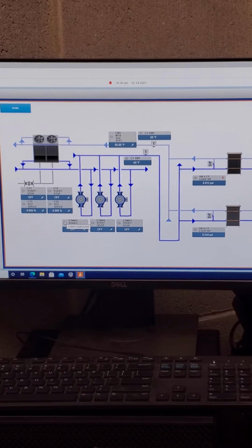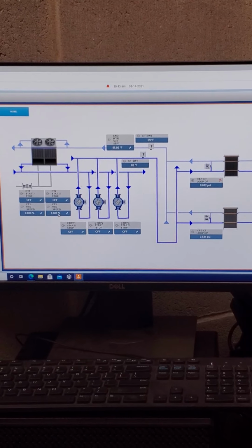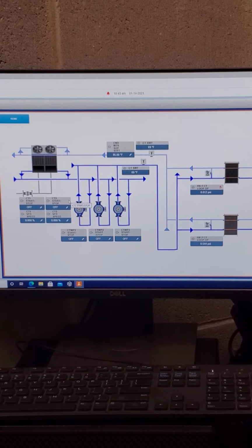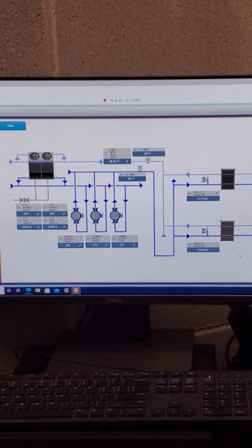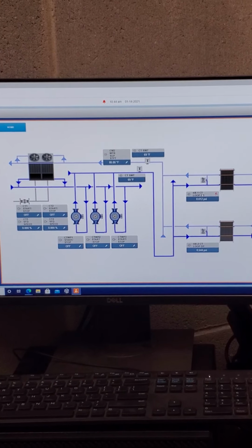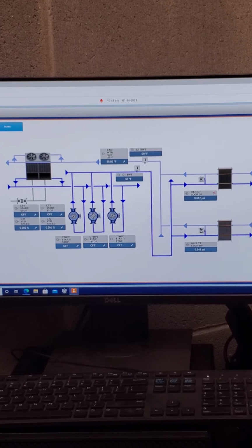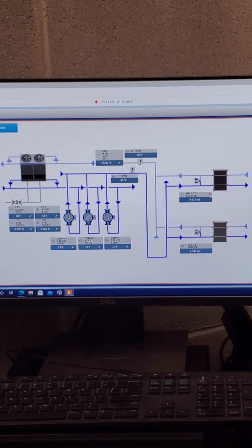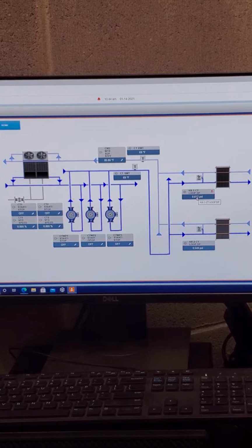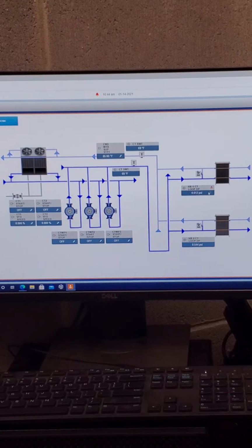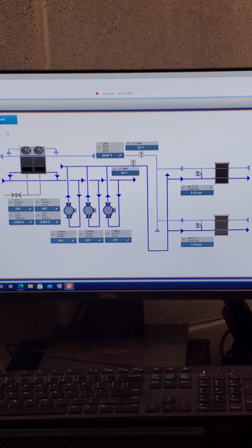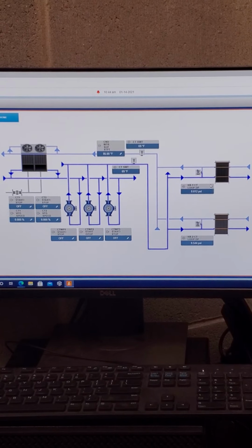We still can see, let me think here, I believe we still have a proof on this. We should still see an alarm if they're not running. And this point is actually an alarm right now. That may be a product of what the alarm levels are set at, but we can look into that. That's what an alarm will look like on the graphic as an example.